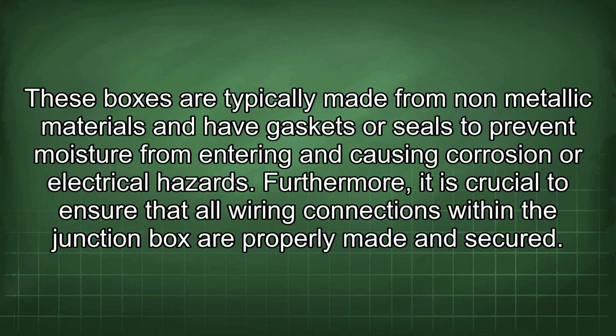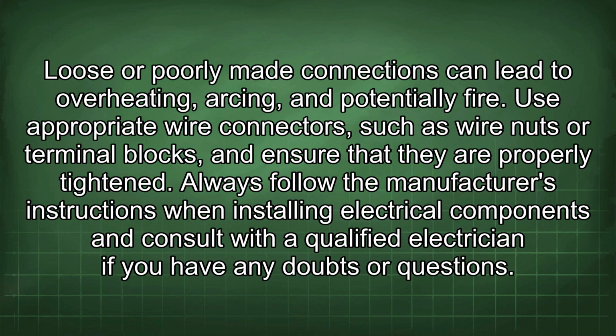Furthermore, it is crucial to ensure that all wiring connections within the junction box are properly made and secured. Loose or poorly made connections can lead to overheating, arcing, and potentially fire. Use appropriate wire connectors, such as wire nuts or terminal blocks, and ensure that they are properly tightened.